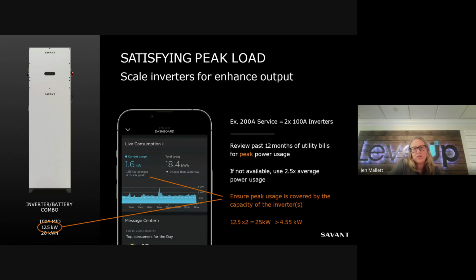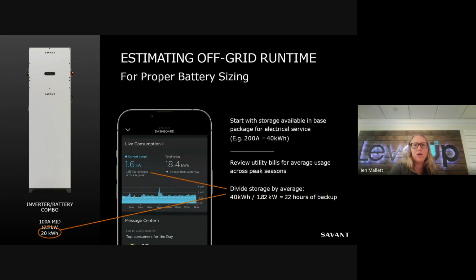Scale inverters enhance the output. So in this case, going back to the original example, we had 200 amp service with 2 times 100 amp inverters. Reviewing the last 12 months of the utility bill, what is that peak power usage? If not, use the 2.5 average power usage we used on the previous slide. And you want to make sure that the peak usage is covered by the capacity of the inverter, because if it's not, it's not going to be able to satisfy that peak load.